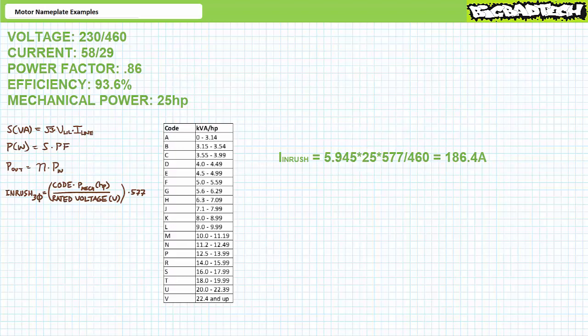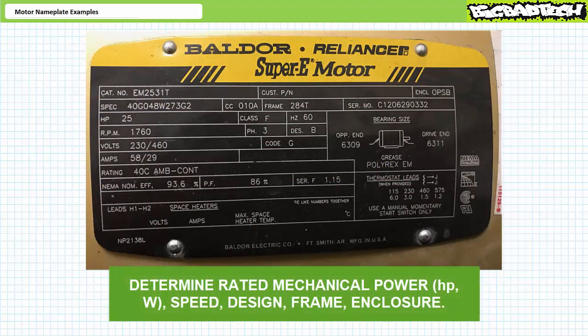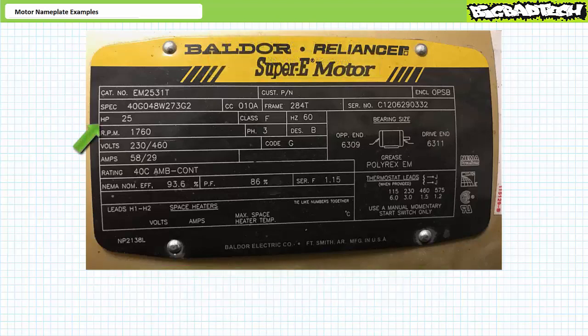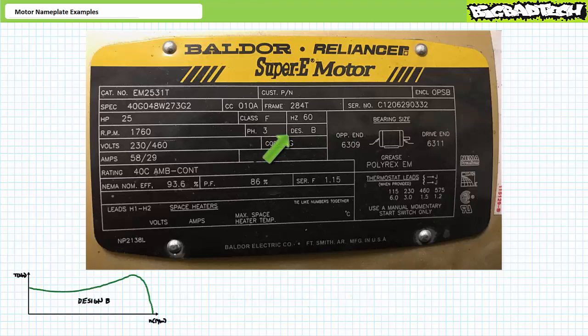I believe we've thoroughly examined the electrical aspects of this motor. Let's take a quick look at some of its mechanical characteristics. See if you can determine the rated power in horsepower and watts, the rated speed, the design, the frame, and the type of enclosure. If you're tracking, you should find this is a 25 horsepower motor operating at a rated speed of 1760 RPM — roughly equivalent to 18.7 kilowatts. It is a NEMA Design B general purpose induction motor, which has a characteristic speed-torque curve.